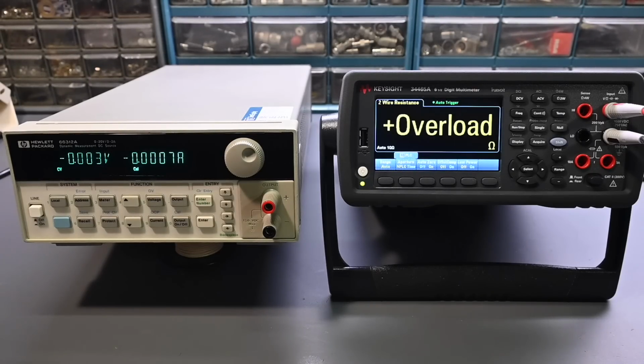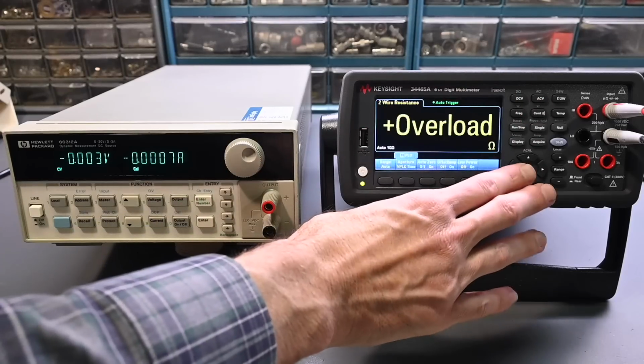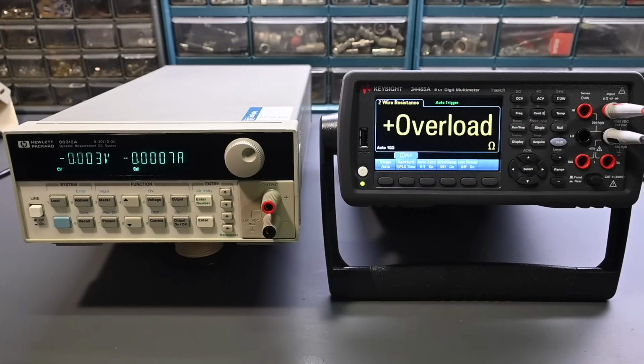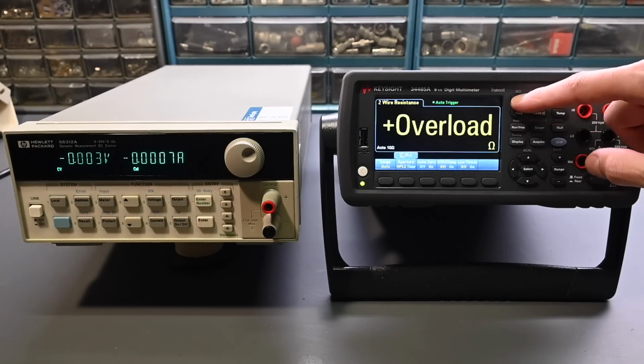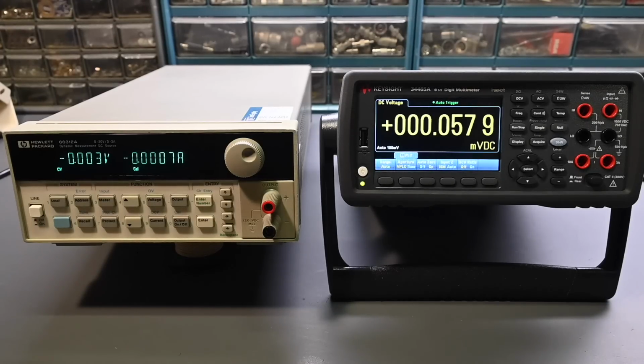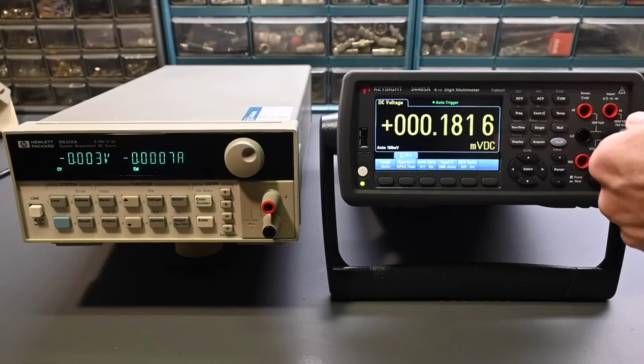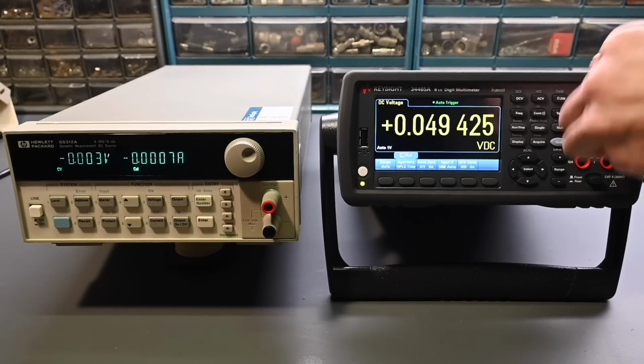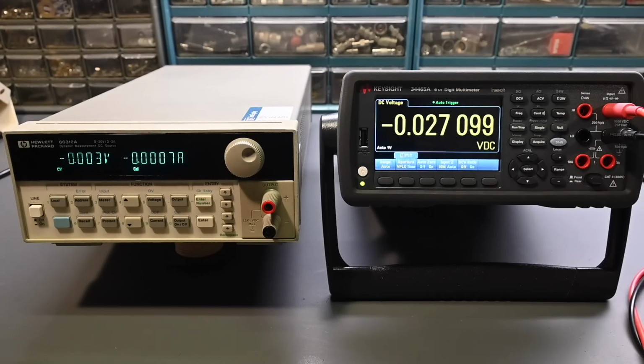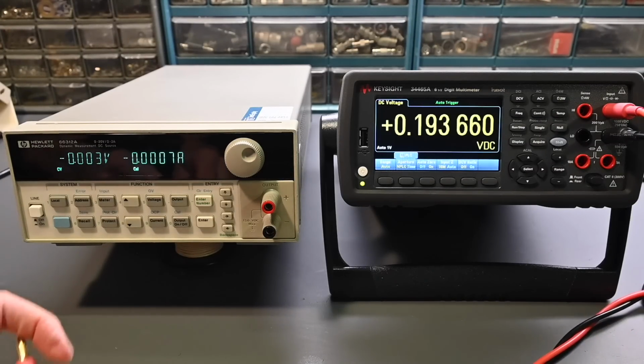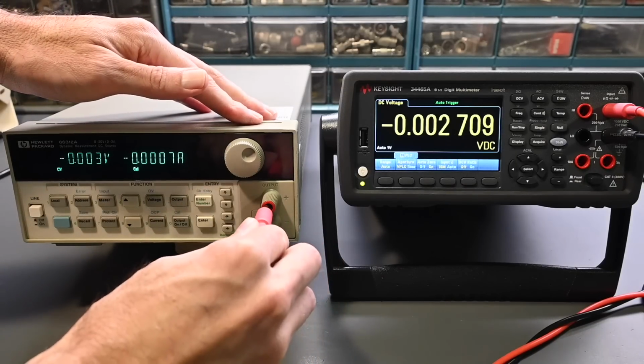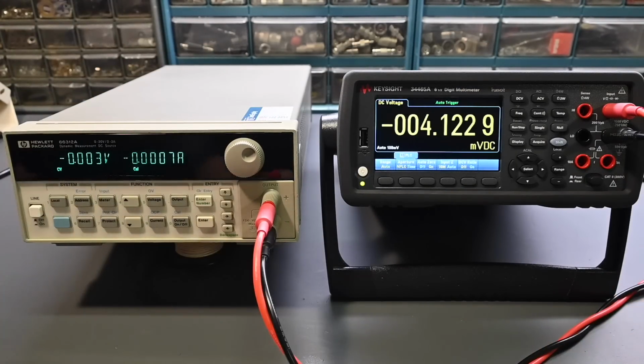So now it says to connect the digital multimeter in the DC volts mode directly to the DC source. Do not connect the load resistor or current shunt. Also, I'm not going to be using the current shunt. I'm just going to rely on the current measurement of this meter when we get to that point. So let me reach around on the other side of the camera here. I'm going to change these test leads. Let's get this back to DC volts. Get this plugged in right here. The test leads are wrapped around each other as well, just to help eliminate any noise pickup. Okay, so that gets everything connected there.